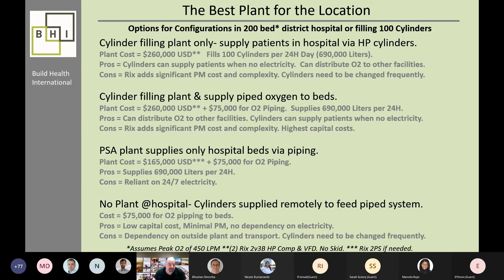Accurate sizing of the plant is critical. Obviously, if it's too small, there's not enough oxygen for the population. And also, if the demand for oxygen exceeds what can be produced, the oxygen purity can be impacted. But also, if the plant is too large, there are also problems. Not only do the capital costs greatly increase with the size of the plant, but your preventative maintenance costs really go up. And it's something you have to think about, especially if you are funding a plant for a hospital or NGO, how they are going to afford the maintenance and spare parts for that. Also, the larger the plant, the more electricity is used, and that often is in the form of diesel fuel.